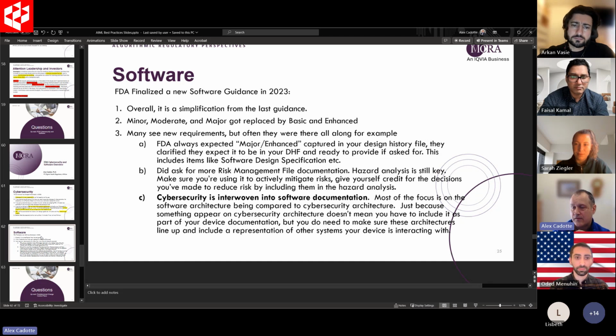The other thing is the risk management file documentation. It used to be the hazard analysis with the old software guidance was the whole point. The whole point of this QMS documentation is to reduce the risk profile of your device by mitigations. They're still going to be looking at that, but they're asking for more things. They're asking for the full risk management file rather than just the hazard analysis. So there are material differences for those things.